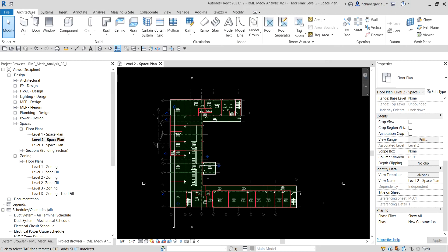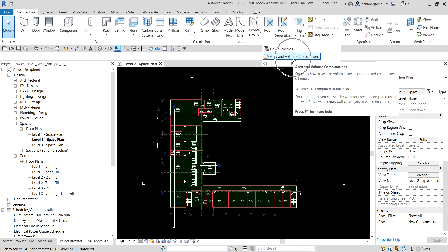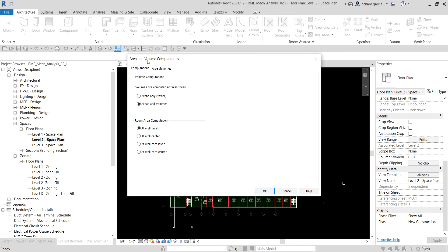Next, verify the Area and Volume settings. Go to the Architecture tab, open the Room and Area panel, and click Area and Volume Computations. Under Volume Computation, the Areas and Volumes option must be selected in order to perform an accurate heating and cooling loads analysis. If after opening the Heating and Cooling Loads tool you receive a message that this option is not checked, the space volumes will be approximate. Confirm it is selected and click OK.